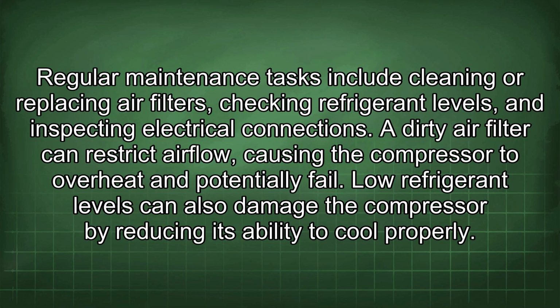Proper maintenance is critical for extending the lifespan of a hermetic compressor. Regular maintenance tasks include cleaning or replacing air filters, checking refrigerant levels, and inspecting electrical connections. A dirty air filter can restrict airflow, causing the compressor to overheat and potentially fail. Low refrigerant levels can also damage the compressor by reducing its ability to cool properly.